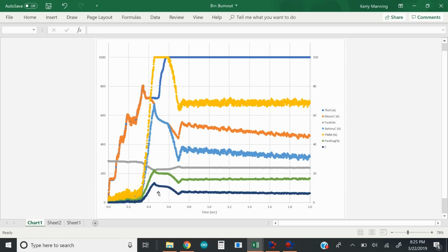The key thing you want to look at with these C rates, or whatever you discharge, is what happens to the voltage. This battery pack started off at 285 volts, then sagged down to about 230. That sag is the relation of the starting voltage versus the voltage under load - the voltage will drop as you start pulling current out of it.